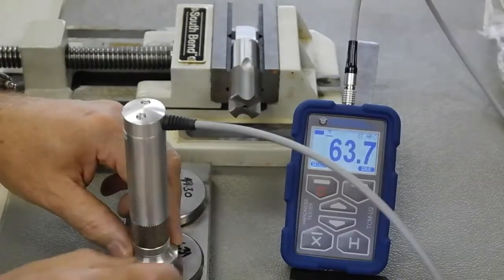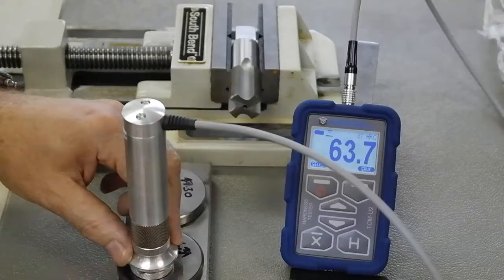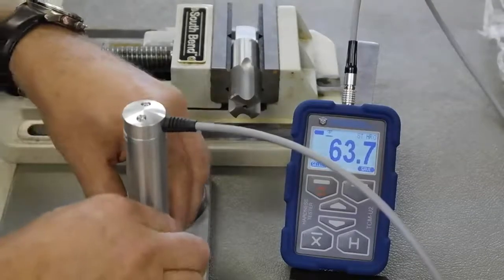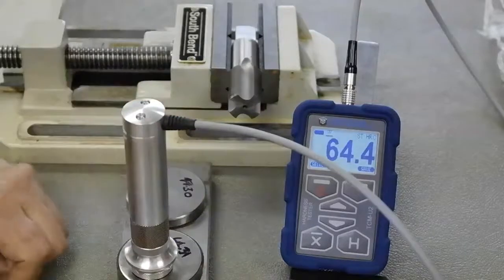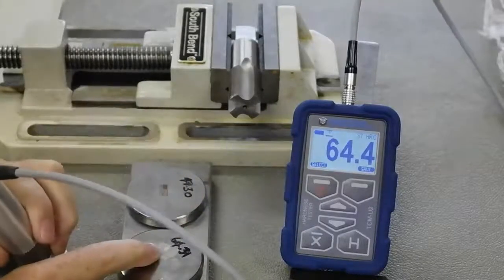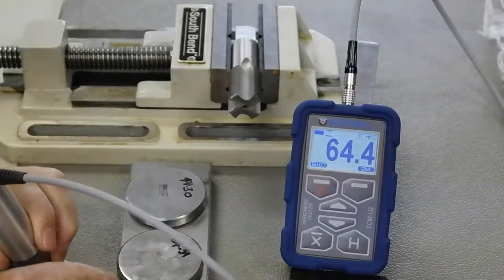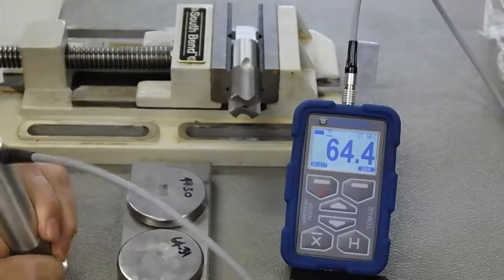I could also set it up to do averaging. So if you do 3 tests, it's going to give you the average of those 3 tests and give you an even more accurate result. So you can see here the test block is 64.3. Its tolerance is plus or minus 0.5. We're right on the money.